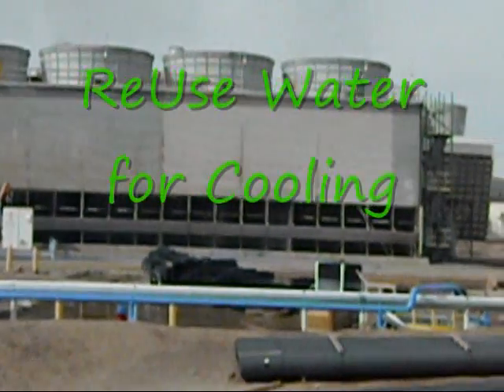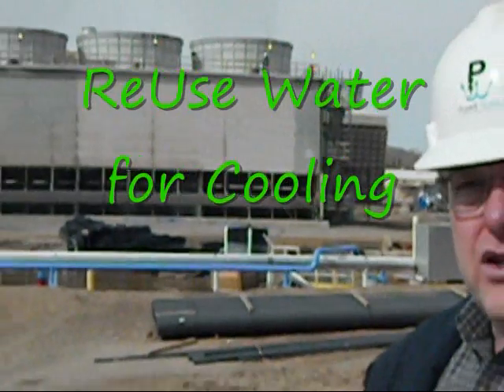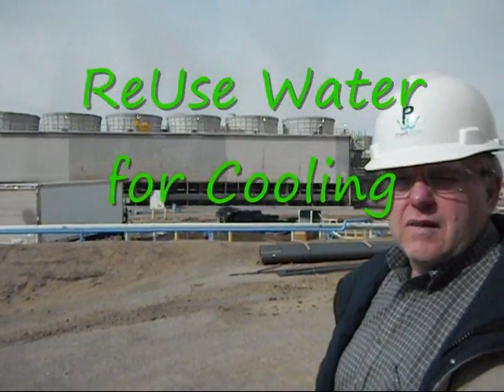The cooling towers can evaporate 2.5 cycles of water before the silica builds up. Silica is their limiting factor. The purpose of the electrocoagulation unit is to separate the silica from the water so that they can increase their use of the water and lessen the amount of water that they have to throw away due to the silica.